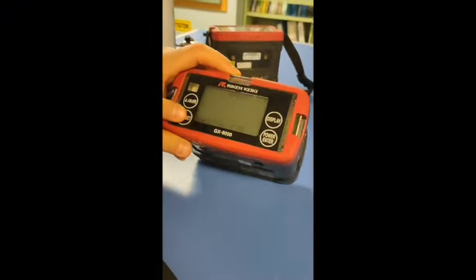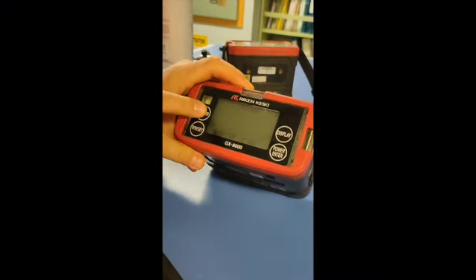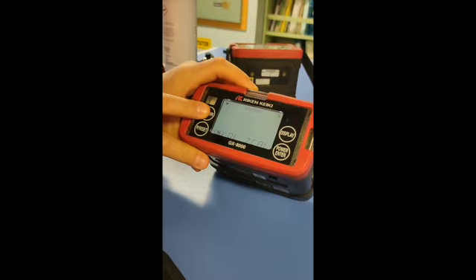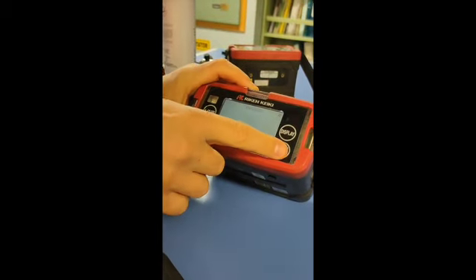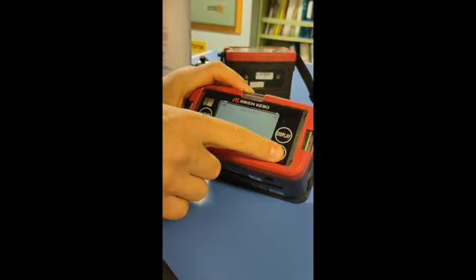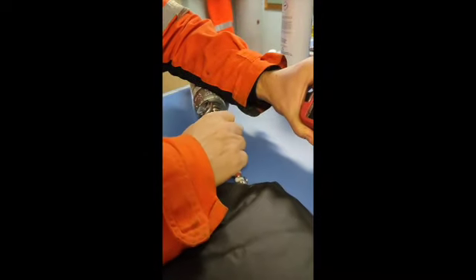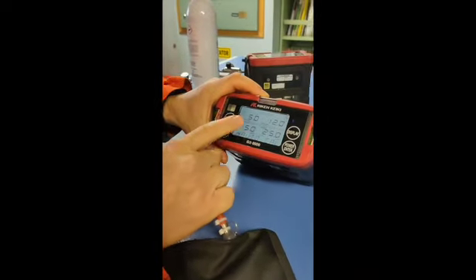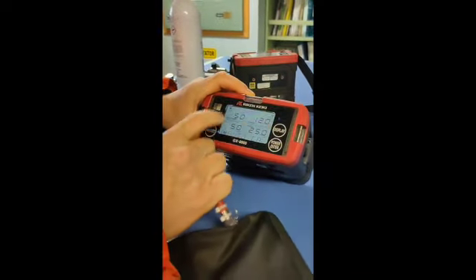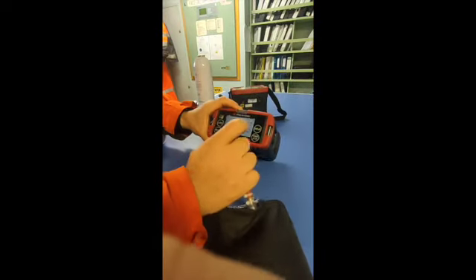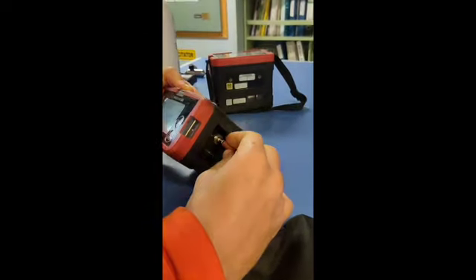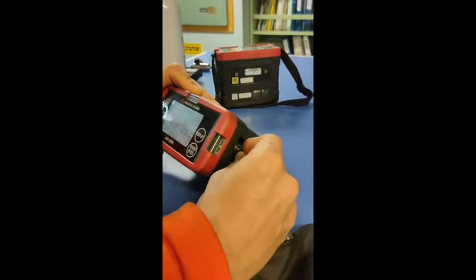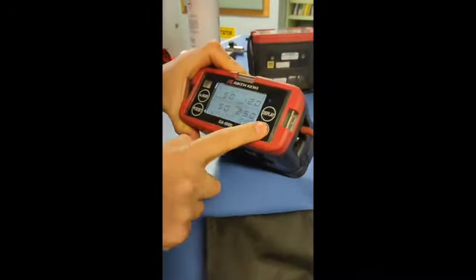As we did the zero cal and air cal, we will go furthermore to the auto cal. So we have to span gas test our 4 gases. 4 gases, not 5 gases. I will let you know later about the 5th one.